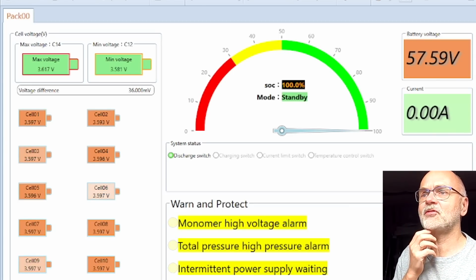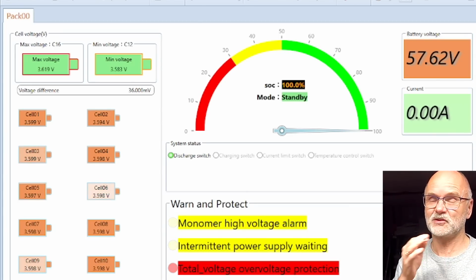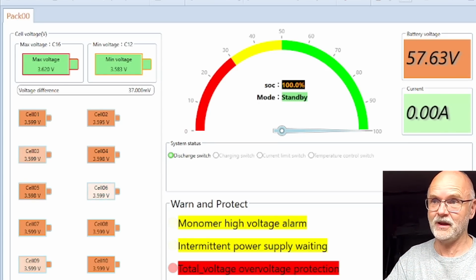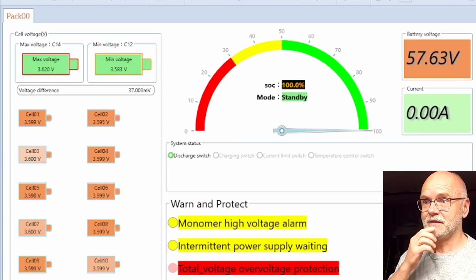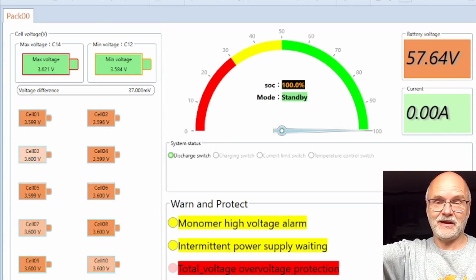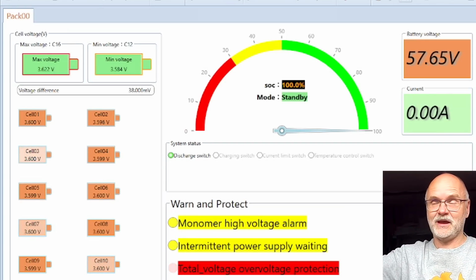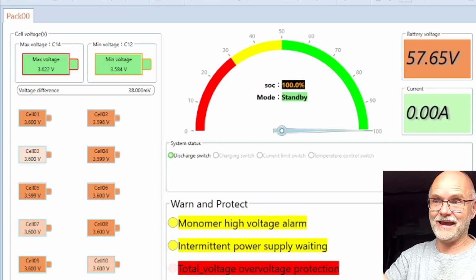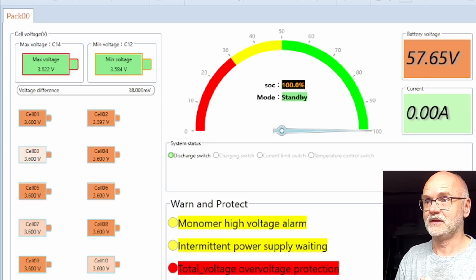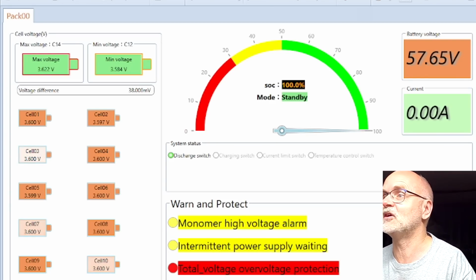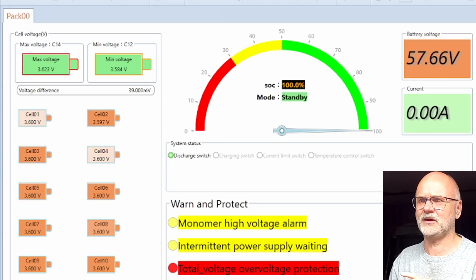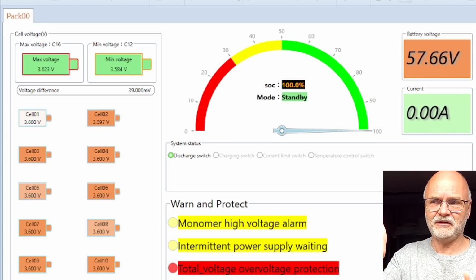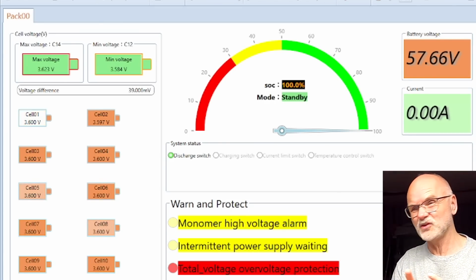And we still have 36 millivolt deviation, so we don't have a cell which is running away anymore. And now the BMS would have shut down everything because we have reached the total pack voltage protection, which is 57 volts or something - yeah, I've seen it too. Still we are at 39 millivolt deviation, so it's not too bad.